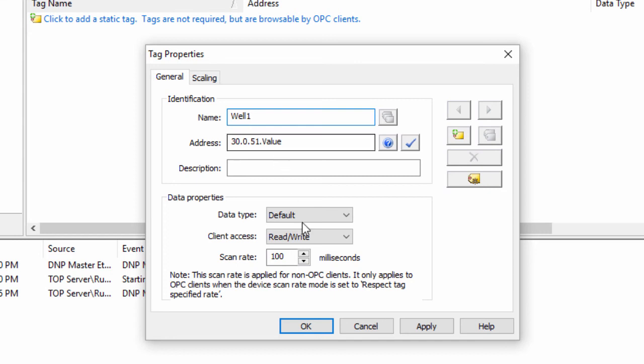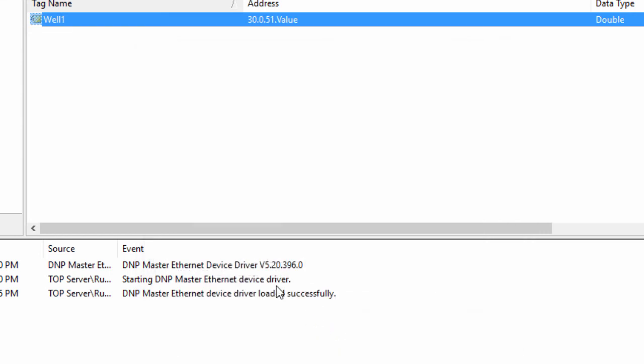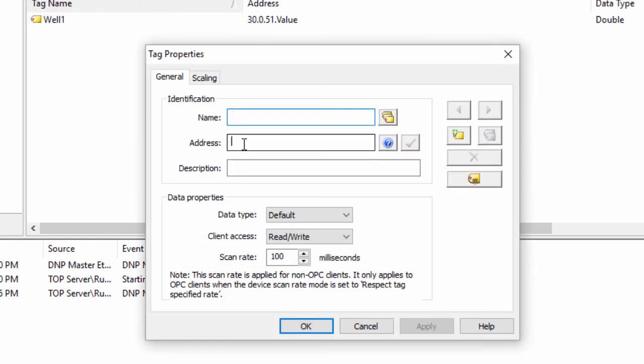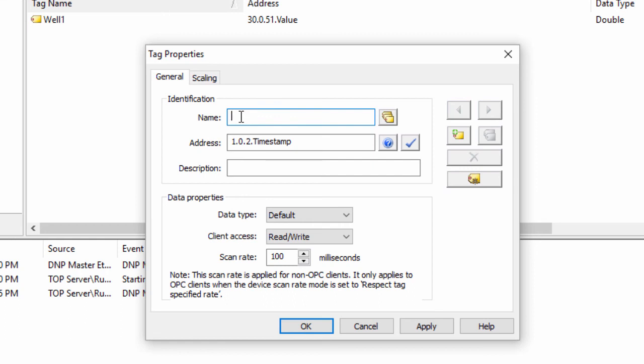Likewise, if we wish to know the timestamp of the event reported on the third binary input, we would define the address 1.0.2.timestamp, where 1 defines the binary input object. 0 defines the default variation. In this case, 2 indicates the third binary input, once again with indexing starting at 0. And timestamp tells us to report the date time of the event value currently reported by the dot value sub-attribute. In the Multismart, this would give us the time of the last station over voltage fault status change, where dot value would show us the status of the fault.